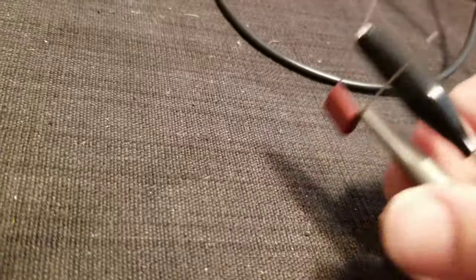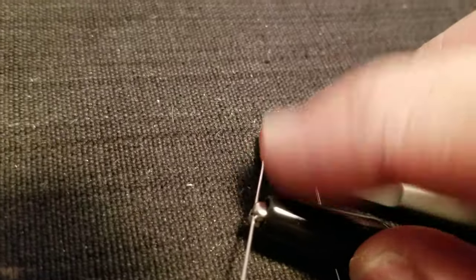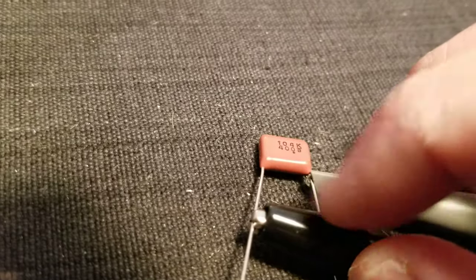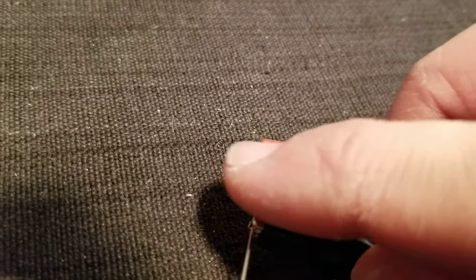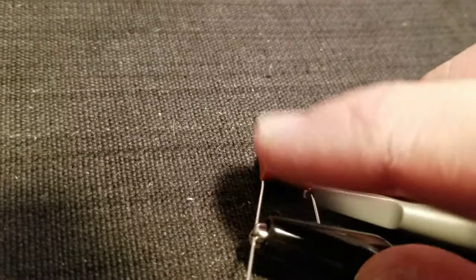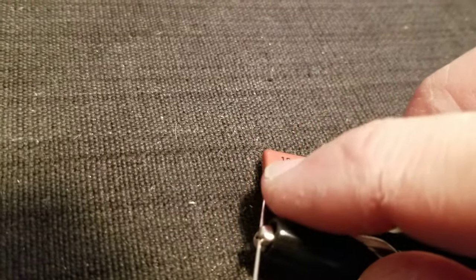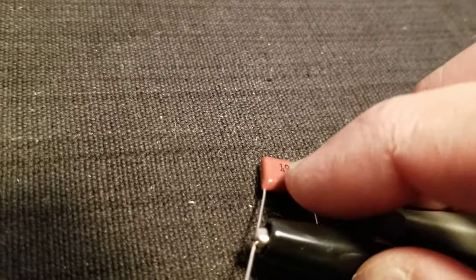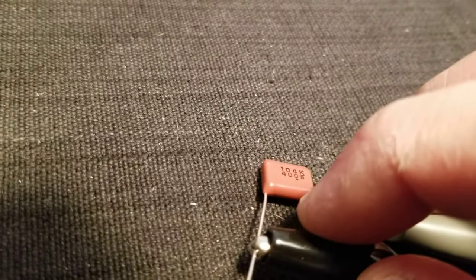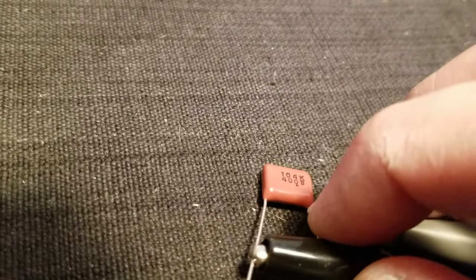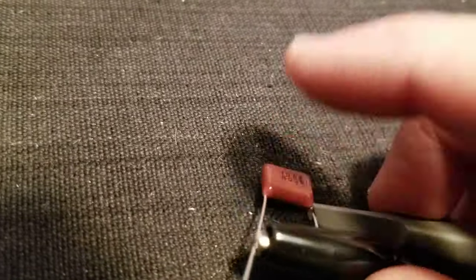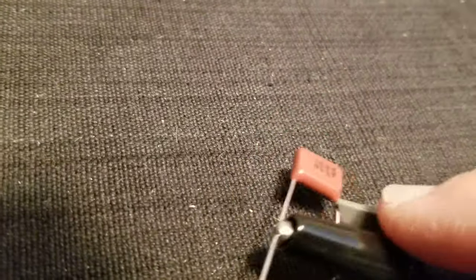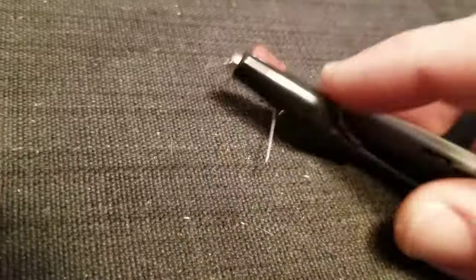So then you can mark it and never assume that the markings on the cap itself are going to tell you anything. I've had, you can have 10 of these caps and they'll all flip flop from one side to the other. The markings don't indicate anything. So just because you test one, you think, okay, well, it's all going to be on this side. No, they're totally different. You have to test every single cap to determine that.